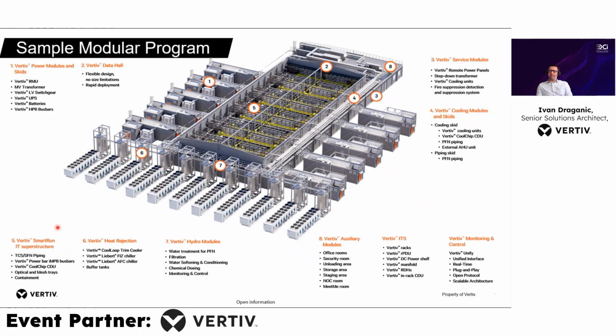We also integrate the control cables and control systems, and a liquid detection system. So if anything leaks, there will be trays for liquid, and there will be liquid detectors that will alert the BMS operator of a leakage. And it's funny, traditionally we never wanted to see water above racks. Oh no, you don't go with water above racks. Well, now we have water inside the racks and it's completely normal, but we're still very worried about liquid leakages. Now more than ever it's critical because there's a lot of fluids, and there are special schemes and ways to deal with that. So that's the inside. We have the SmartRun, a modular infrastructure being brought into the white space.